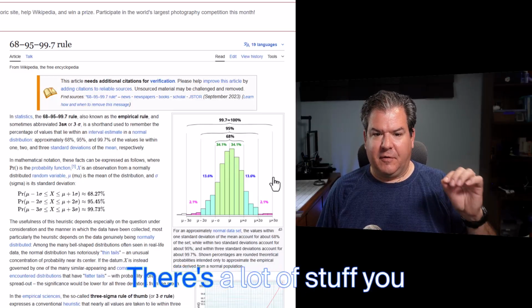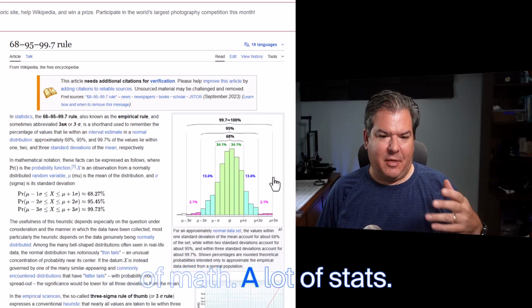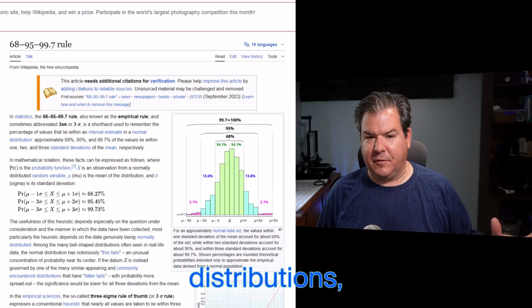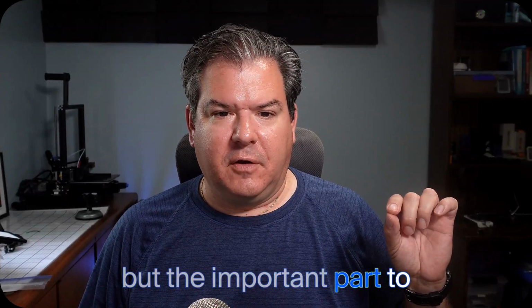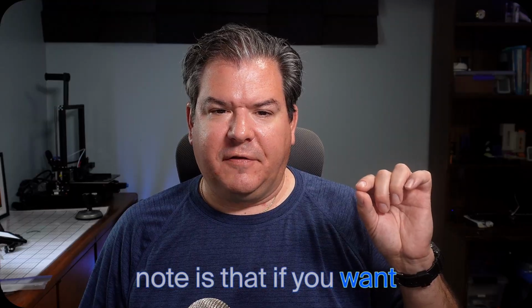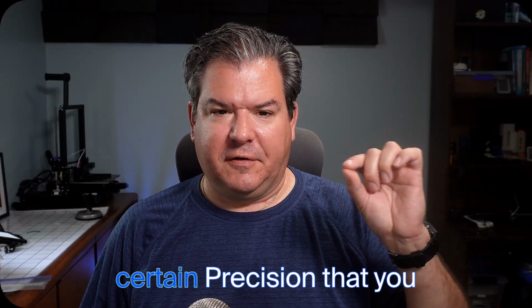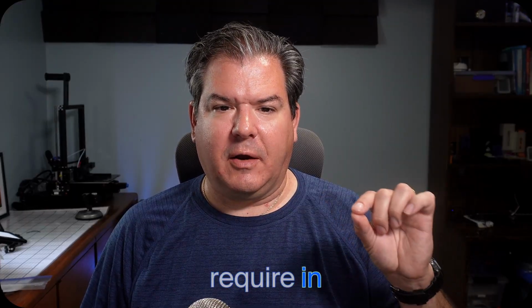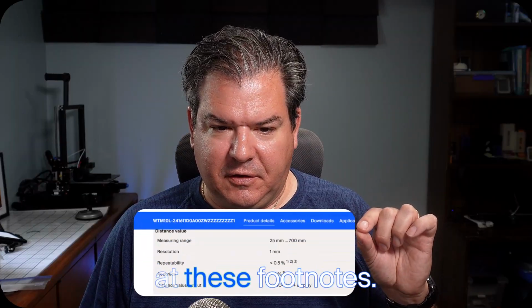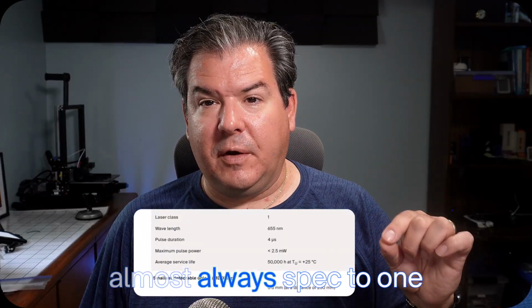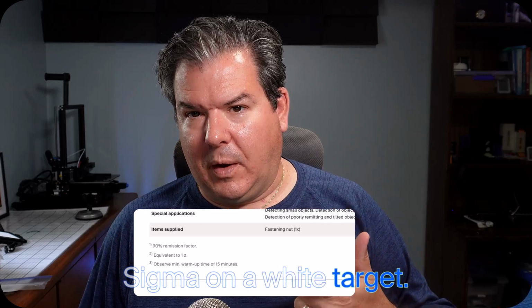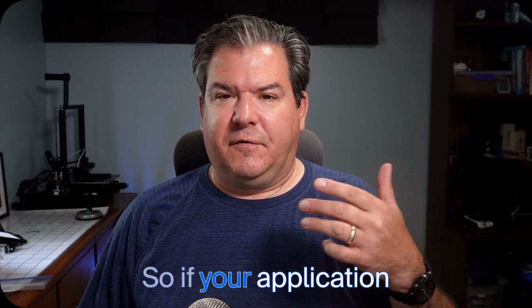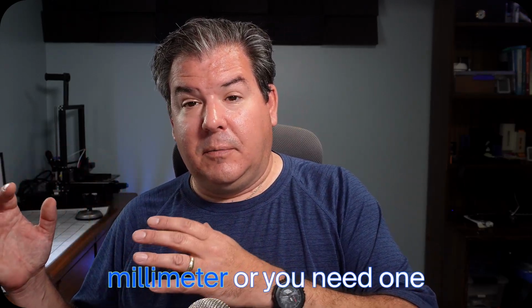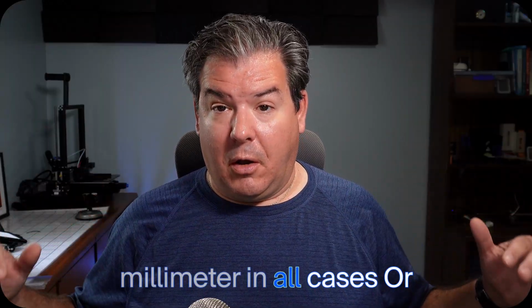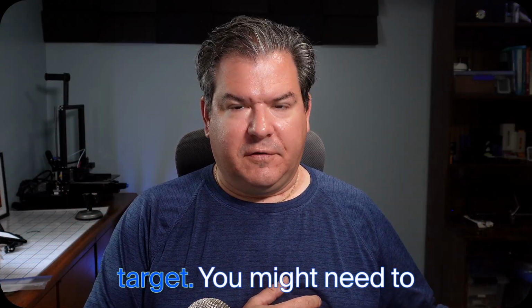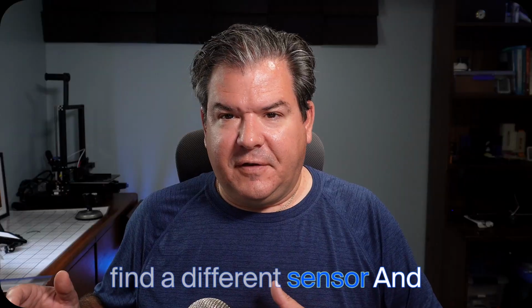So it's very important. There's a lot of stuff you can look into. There's a lot of math, a lot of stats. There are all sorts of different distributions. But the important part to note is that if you want something good within a certain precision that you require, take a look at these footnotes. They're almost always spec'd to 1 sigma on a white target. So if your application needs better than 1 millimeter, or you need 1 millimeter in all cases, or you don't have a white target, you might need to find a different sensor.